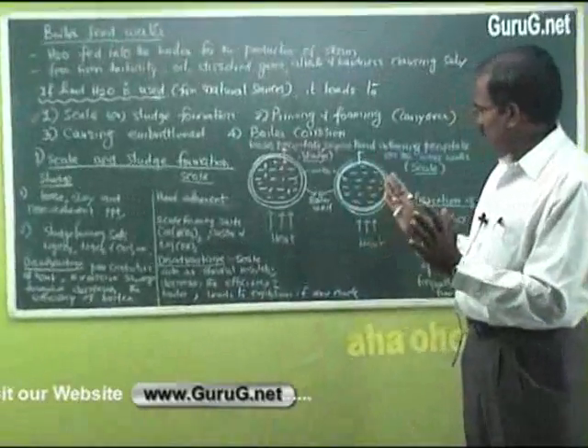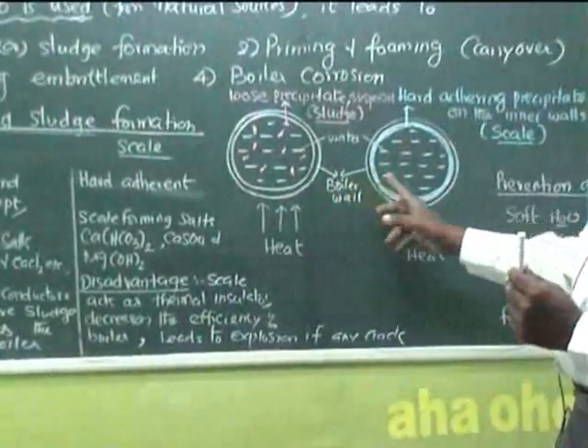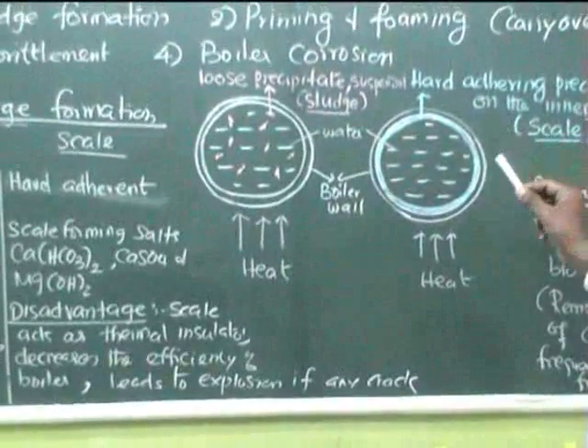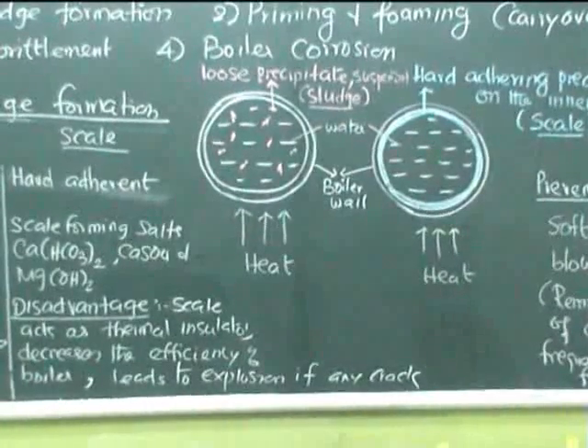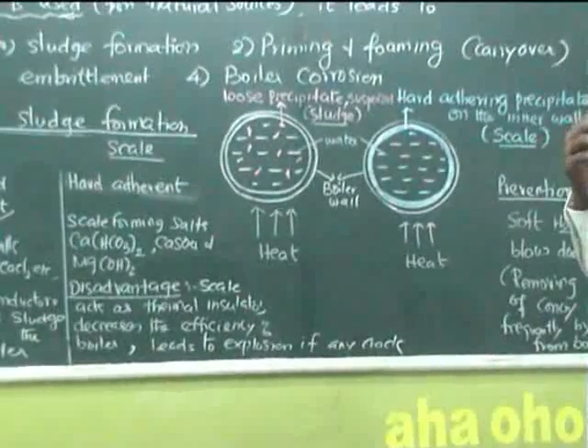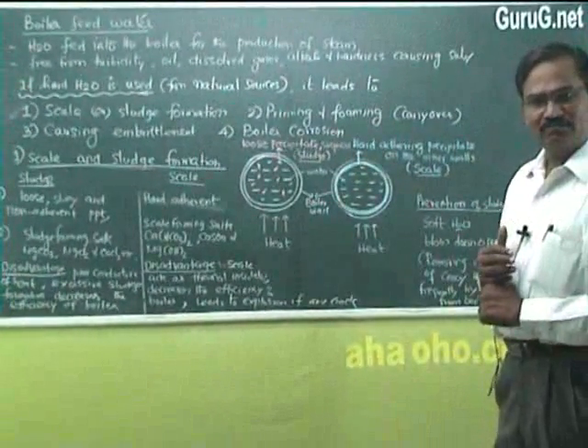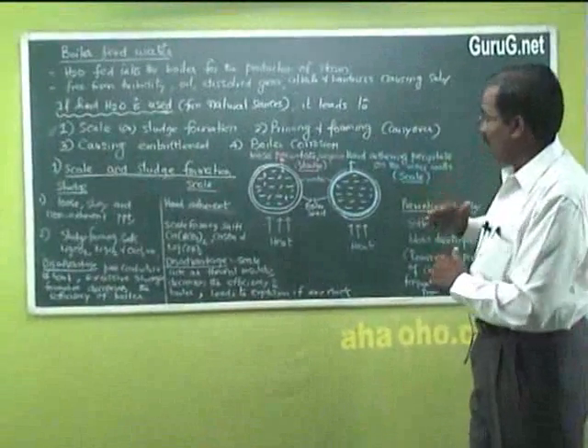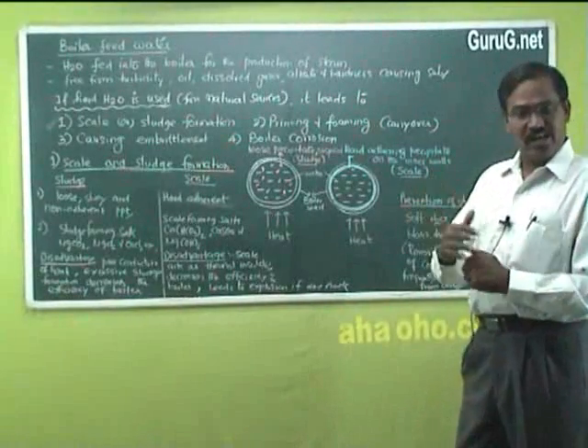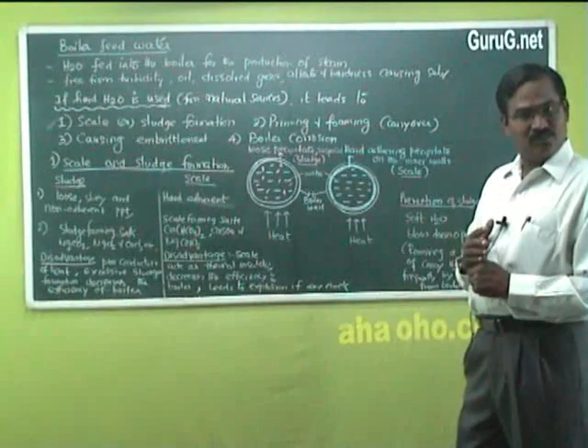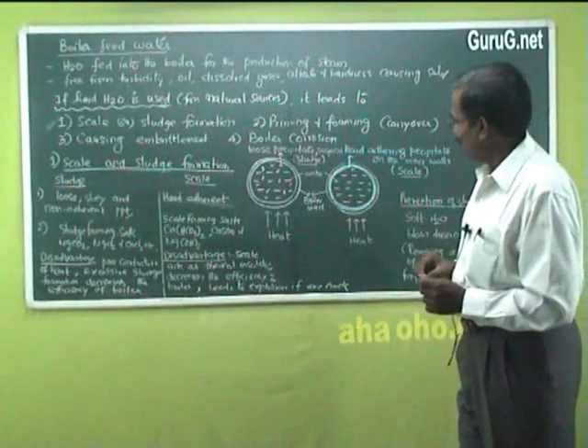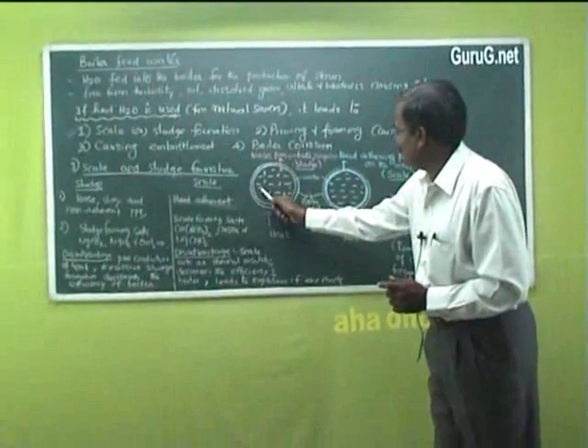This is a boiler. I have taken two things — one to explain scale formation and the other to explain sludge formation. When water is boiled in the boiler, water evaporates and goes out as steam, but the soluble chemical compounds present in the boiler water, since they are highly ionic, remain in the boiler. The concentration of the salt progressively increases until a saturation point is attained. During that saturation point, certain chemical compounds present in the water may appear as precipitate.